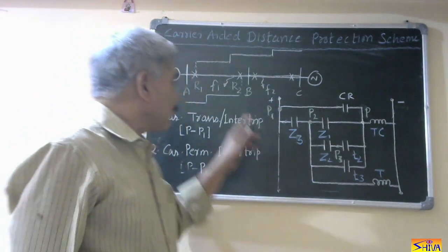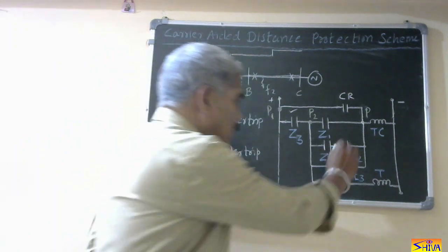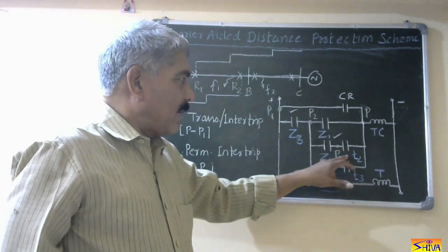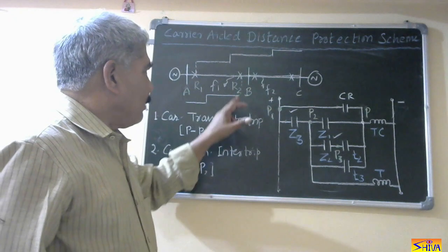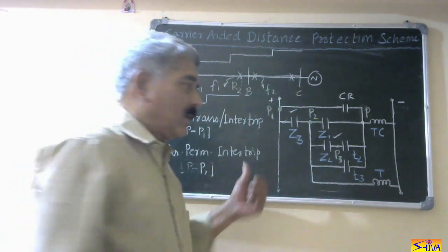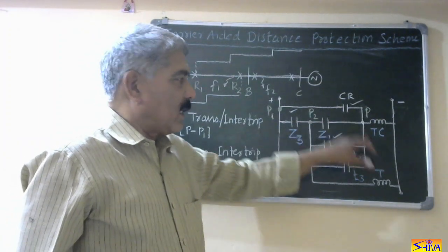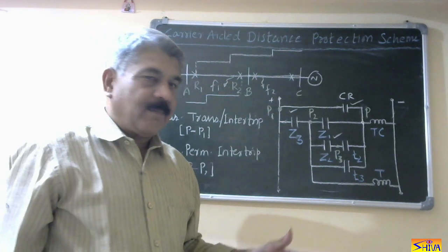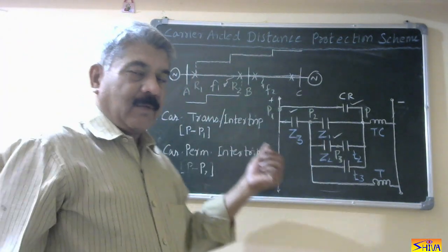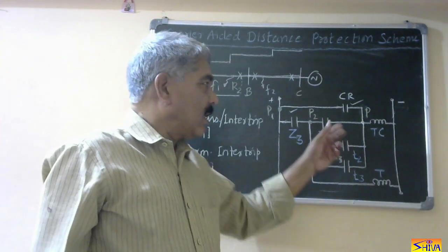Let us see how this scheme works. For fault F1, Z3 will close, Z2 will close, and the timer coil will be energized. If we are not using the CR contact, then after time T2 the trip coil of the circuit breaker would be energized. But carrier signals are transmitted from relay R2 to relay R1. As soon as these signals are received, this contact closes. As soon as this carrier receive contact closes, the trip coil of the circuit breaker is energized immediately — we do not wait for time T2. The circuit breaker will operate immediately as soon as the carrier receive relay contact closes.